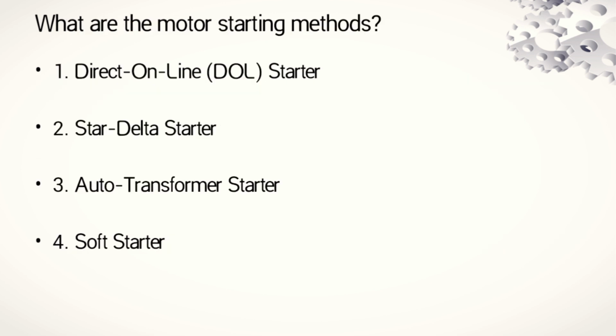And what are the motor starting methods? We have 4 motor starting methods. The first one is the DOL. The DOL is basically the direct online starter. And we have the star delta starter. Third, we have the auto transformer starter. Auto transformer starter is basically automated from the transformer unit. And we have the soft starter.